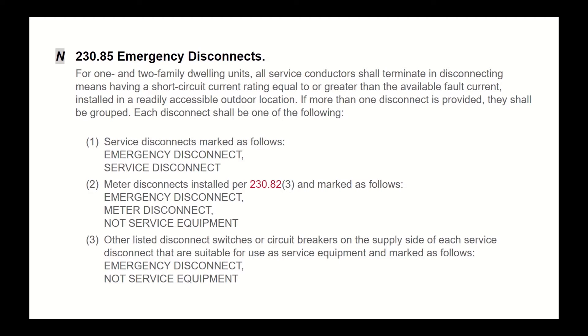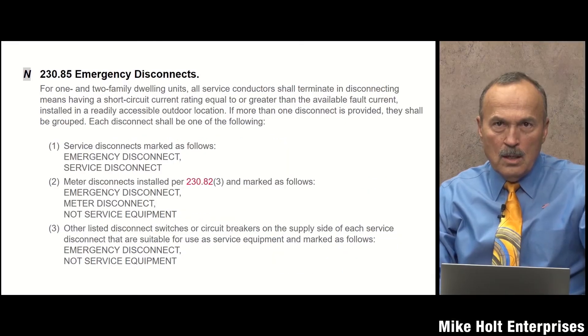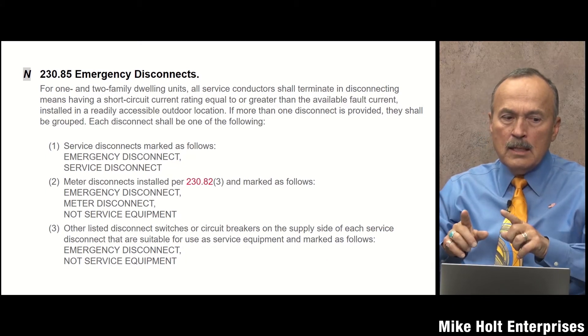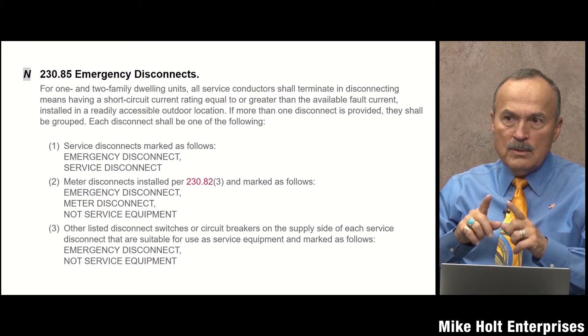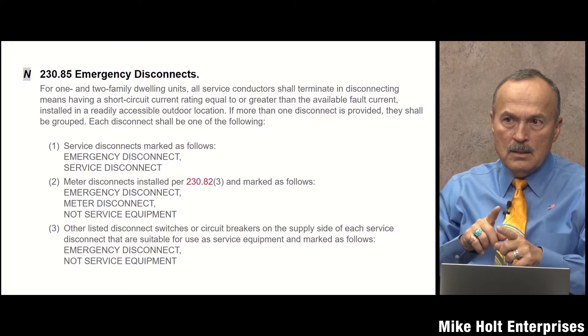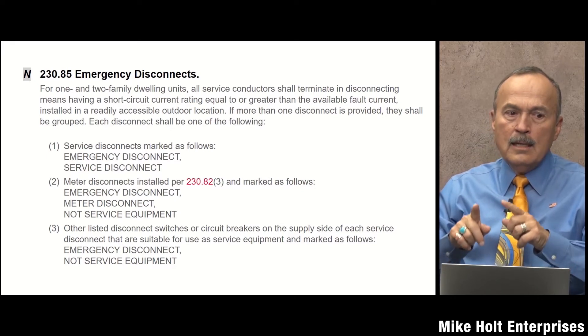The last option is other listed disconnects or circuit breakers on the supply side of each service disconnect that are suitable for use as service equipment. So you can put a disconnect that's rated as service equipment ahead of the service disconnect.